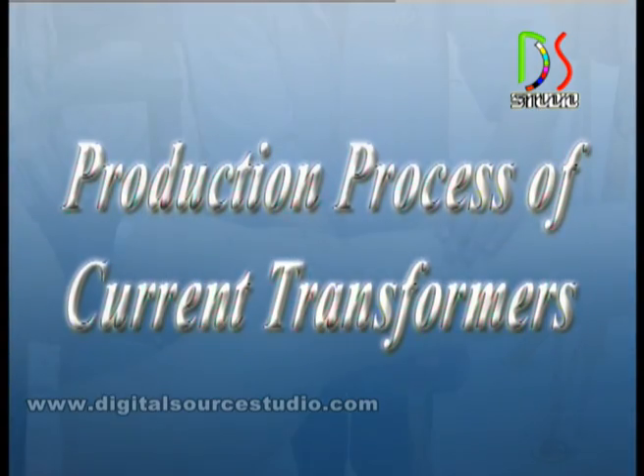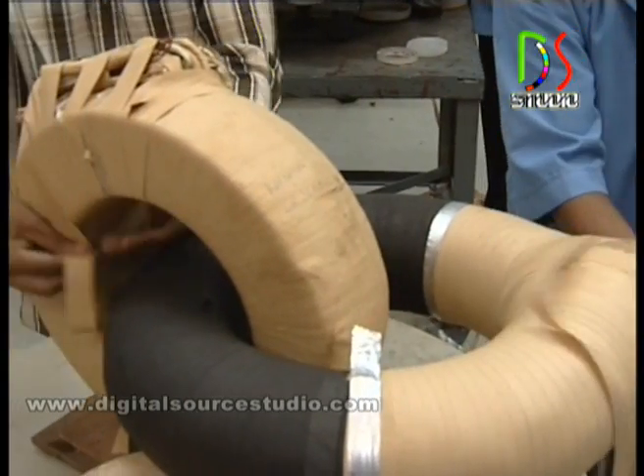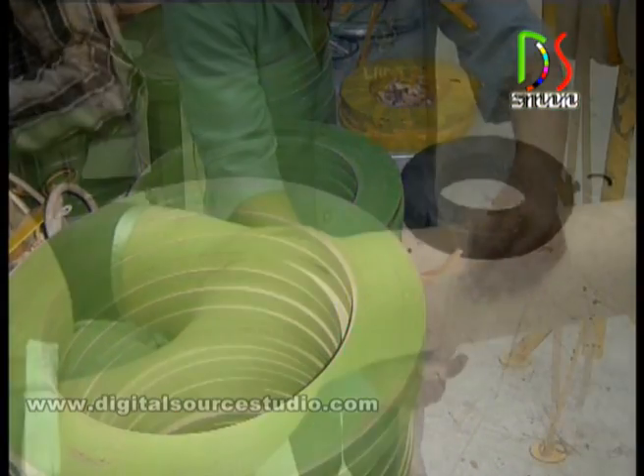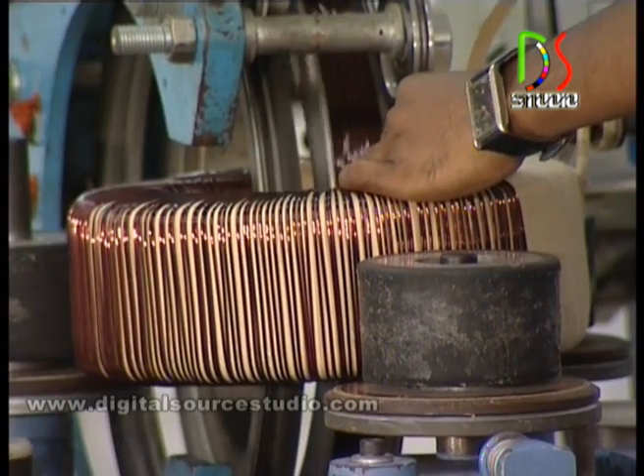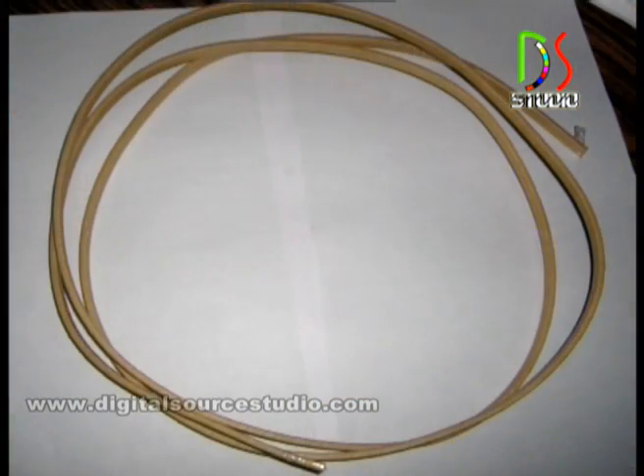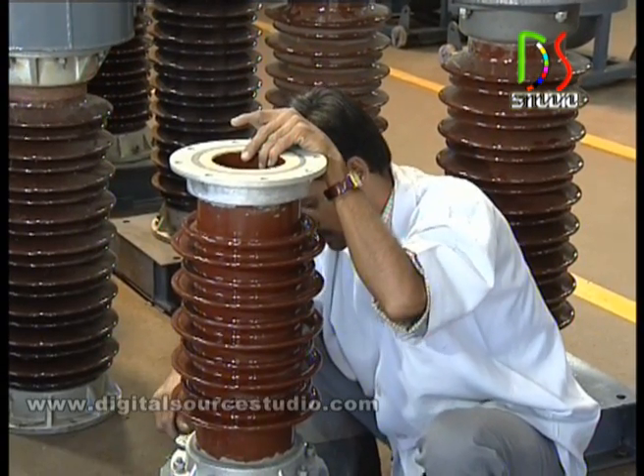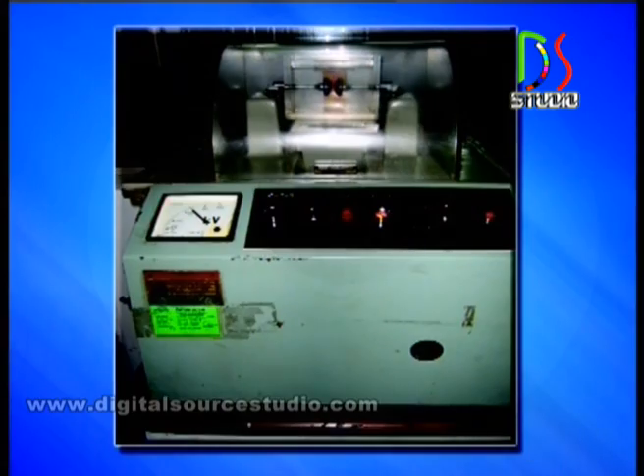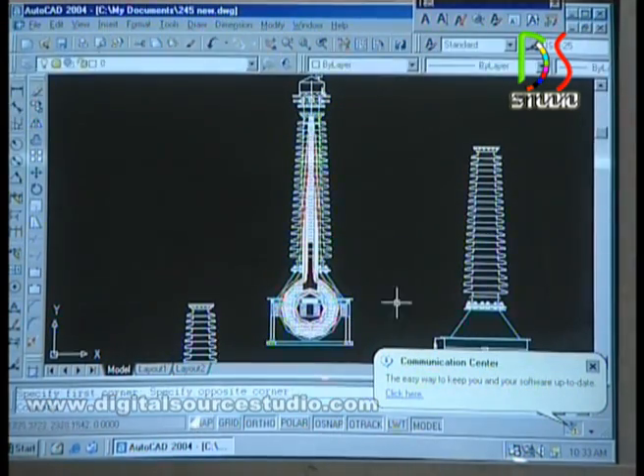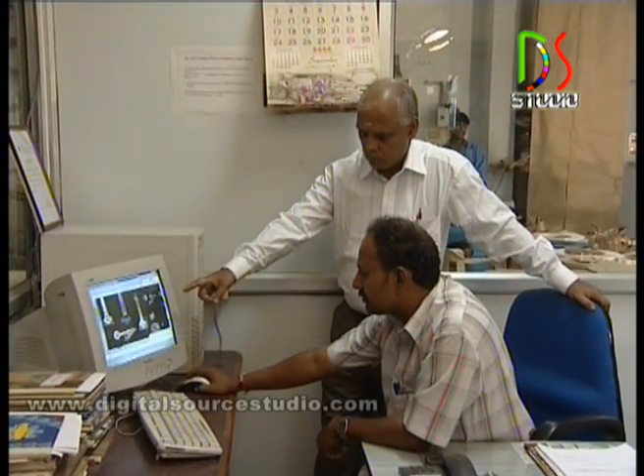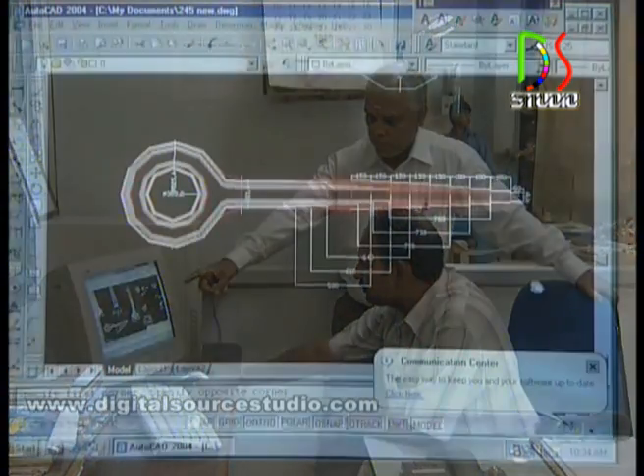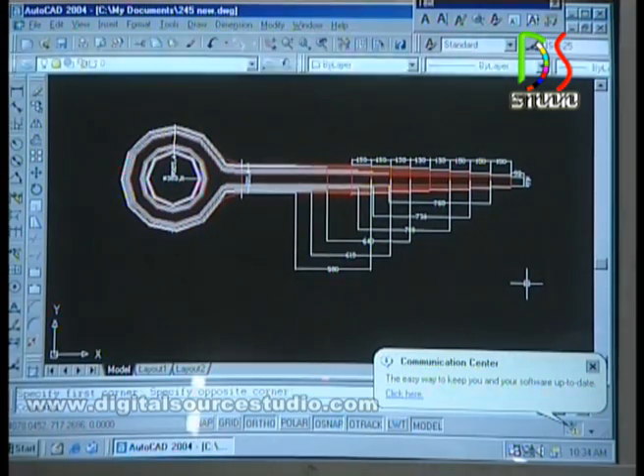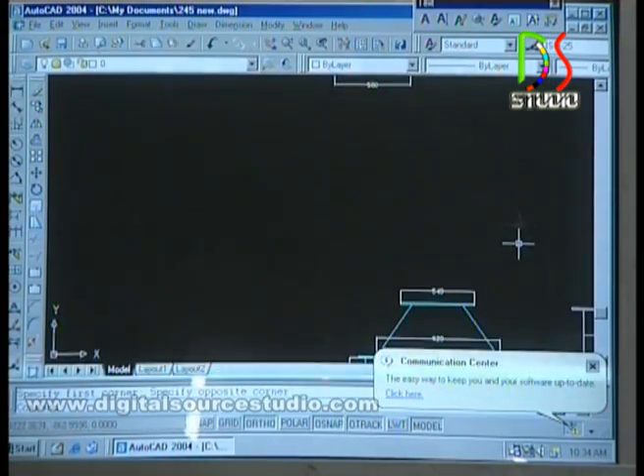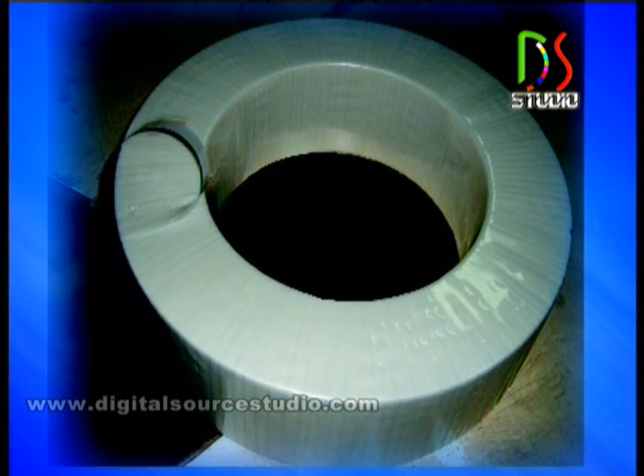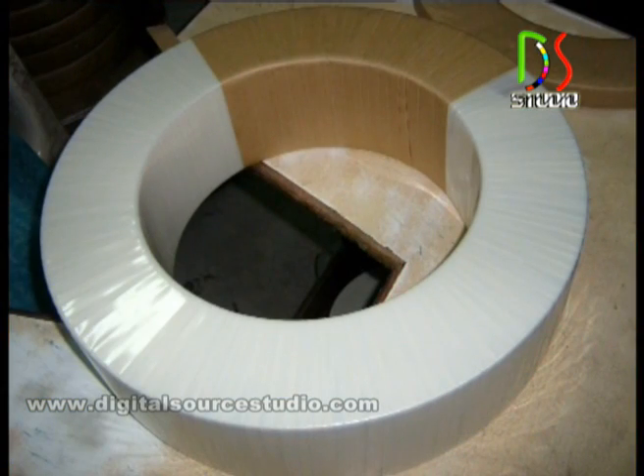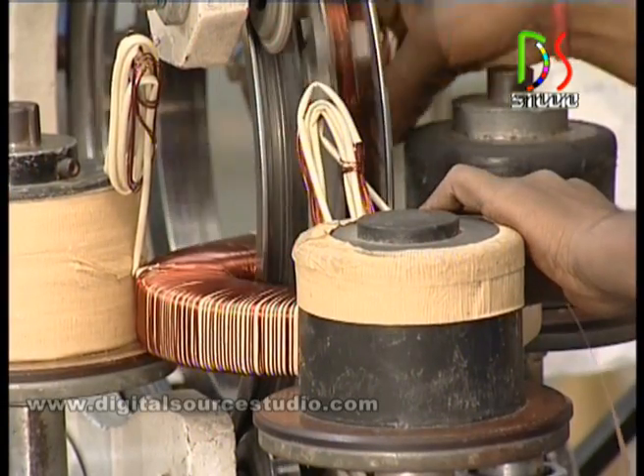Production process of current transformers. The raw materials used in manufacture of CTs are magnetic cores, kraft paper, SE copper wire for secondaries, copper or aluminum ropes for primary, porcelain insulator, polyester film, and transformer oil. The current transformers and potential transformers are designed as per the customer requirement regarding accuracy class, burden, ratio, and other electrical parameters. Bare cores are insulated using polyester film and kraft paper, on which secondary coils are wound.